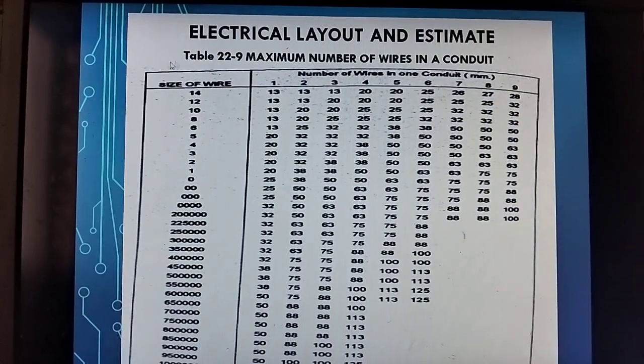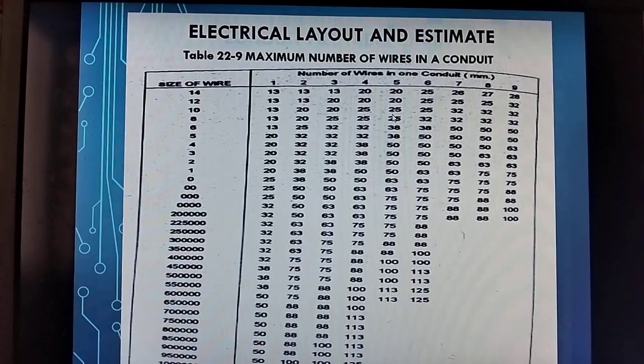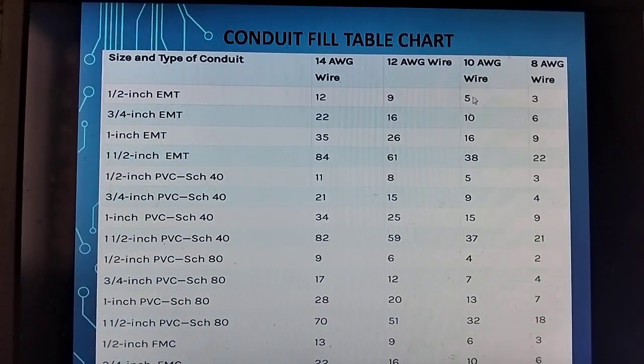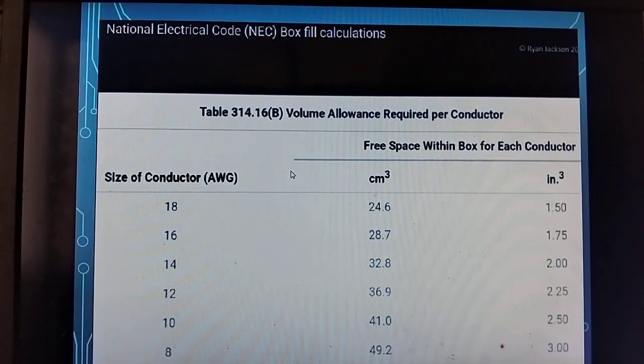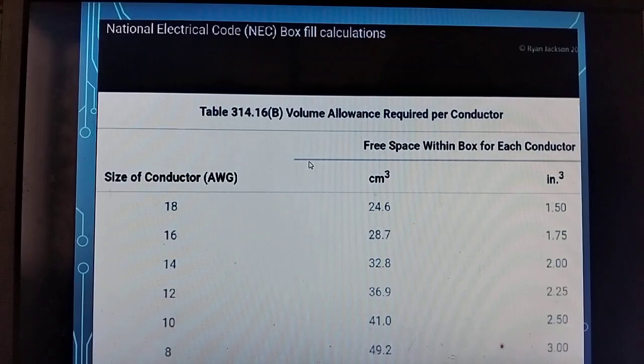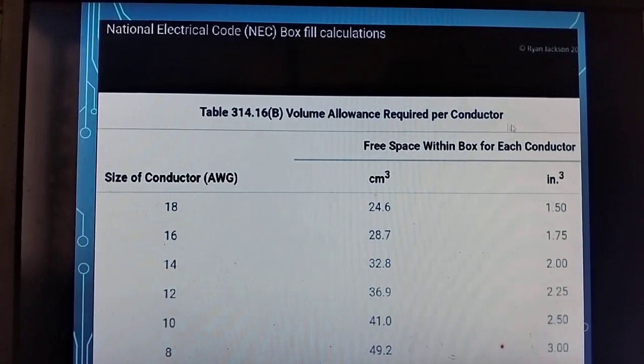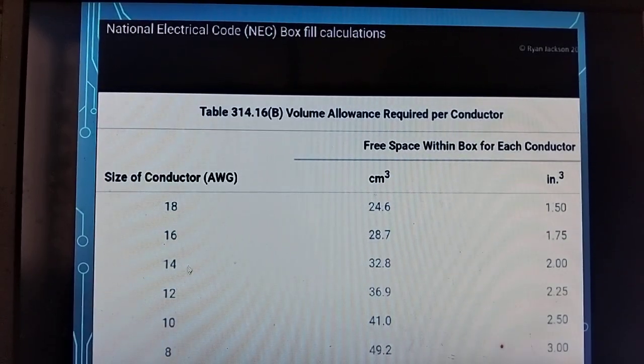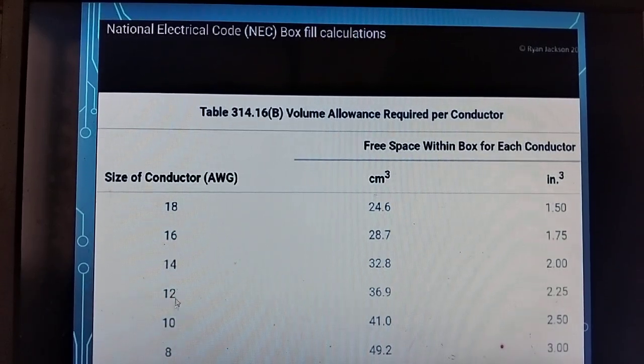So also we have to follow the electrical layout estimate, the maximum number of wires in a conduit. This is also the box fill or conduit fill chart, and also the computation or calculation of the volume allowance required per conductor. Let's say you are going to use size 14 electrical wires. Its volume allowance should be 32.8 cubic centimeters or 2 cubic inches. For size 12 for the convenience outlet, usually size 14 is for the lighting outlet, size 12 is for the convenience outlet, the allowance is 36.9 cubic centimeters and 2.25 cubic inches volume allowance per conductor.